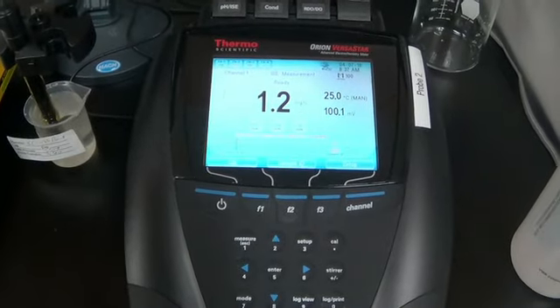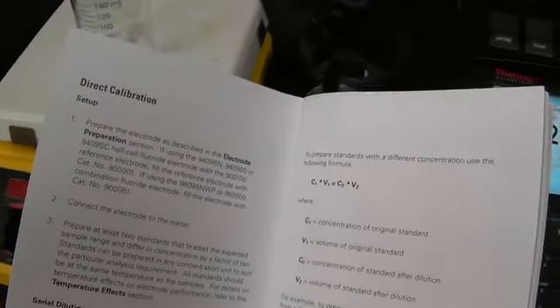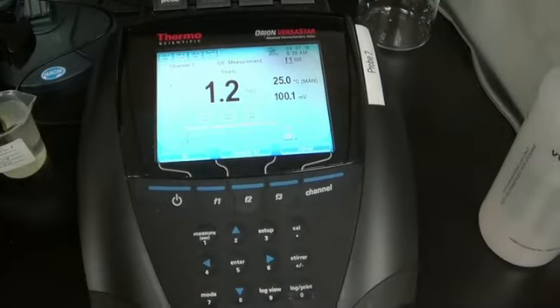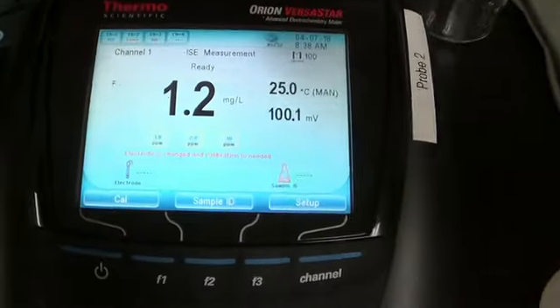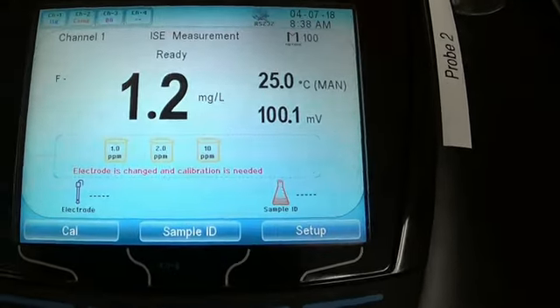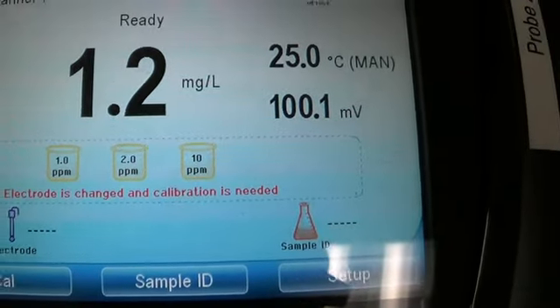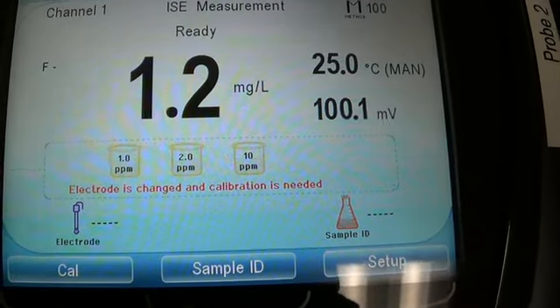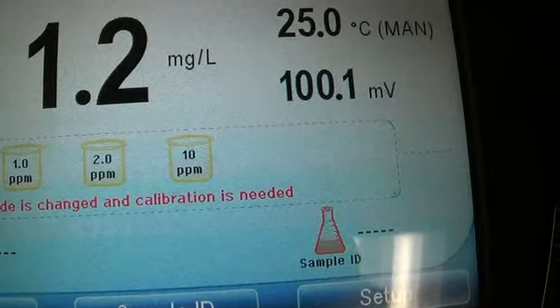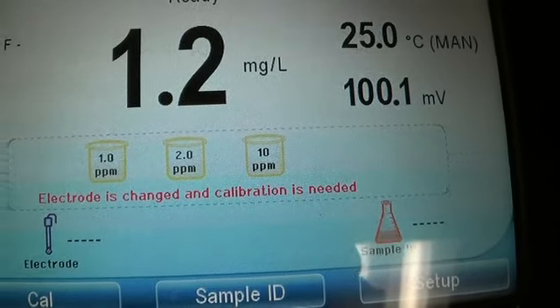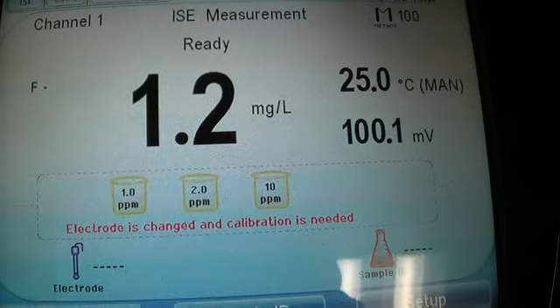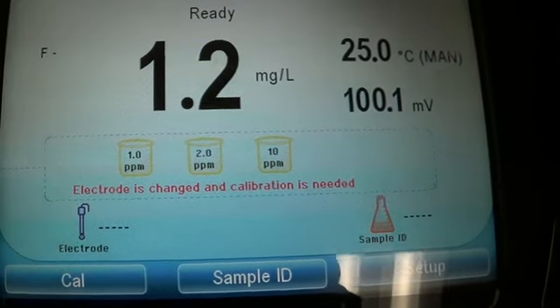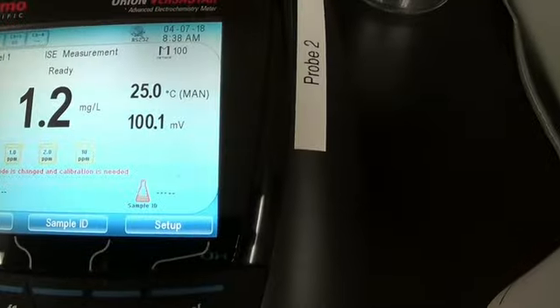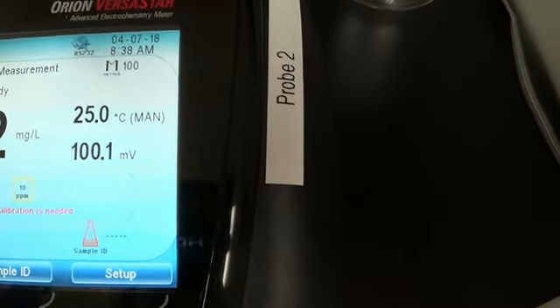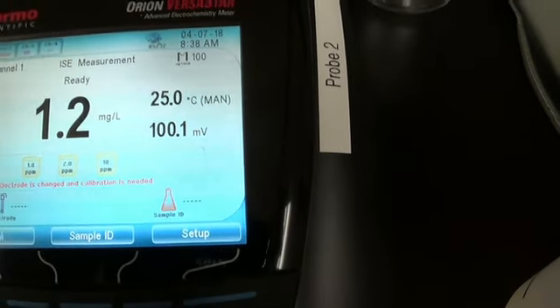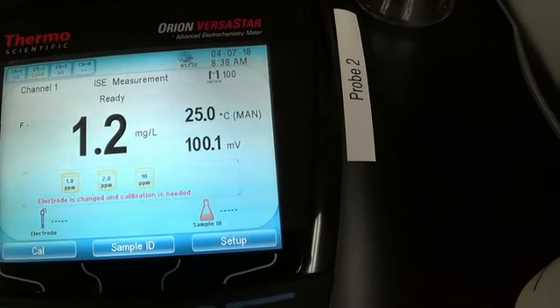Next we're on to calibration, and the book has many different ways to calibrate our instrument for fluoride. Right now we can do it as direct calibration, and there are 3 standards already set up on this instrument. I will be changing them. Right now it's 1, 2, and 10 ppm, which is a bit on the high side. Since we want our water to be 0.7, 0.8, these standards are too high. Another thing we can do is just take the millivolts here. We can make several different standards, take the readings, make a curve, and use that to calibrate.